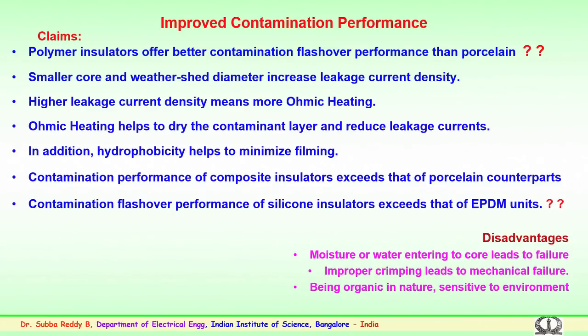Further, improper crimping has to be carefully looked into when the fiberglass rod is being crimped at the edges by the mechanical metallic clamps or the end fittings. So, the proper crimping of these end fittings has to be done with a specified procedure, and the specified hydraulic pressure also has to be taken into consideration.